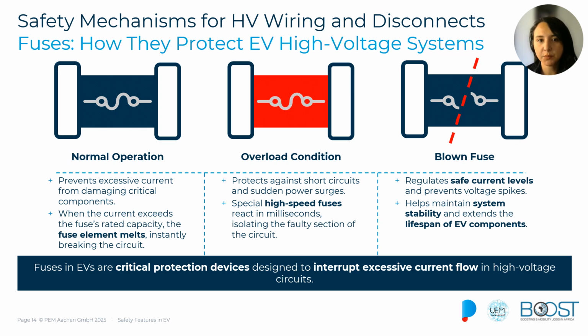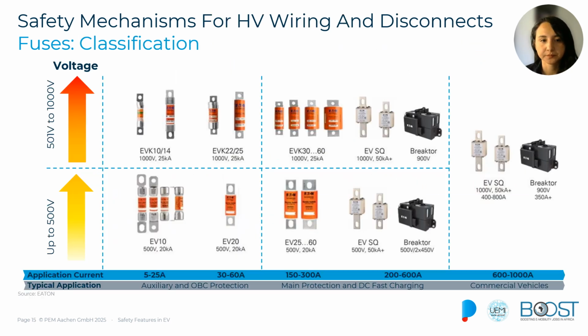We usually use high-speed fuses in this type of system that react in milliseconds, and this ensures that battery short circuits, for instance, are rapidly contained. When we think about fuses, we have to think of them as very important for protecting the battery from overcurrents, and we have to react fast in those conditions. In general, EV fuses are classified mainly based on the voltage rating and the current rating. We have, for instance, fuses that work on the auxiliary systems or in the onboard charger.